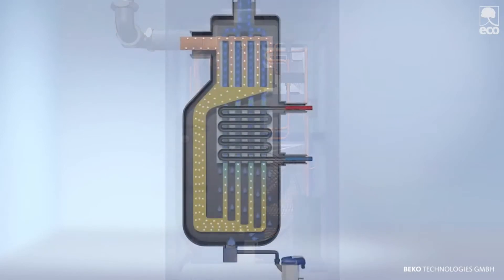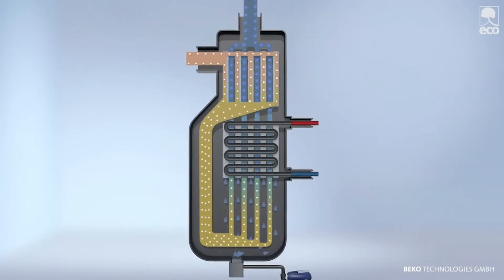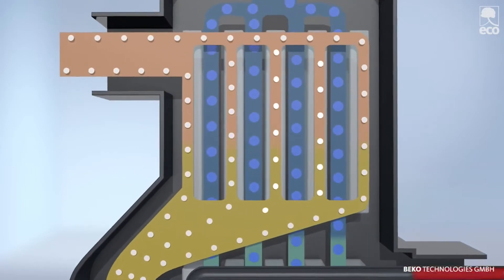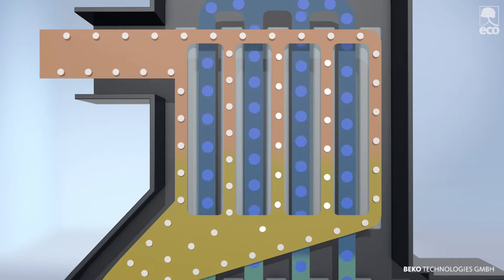Humid compressed air, shown in blue, enters the heat exchanger at the top at about 35 degrees Celsius. There it is pre-cooled in a counter-current process by already dry and cooler air.